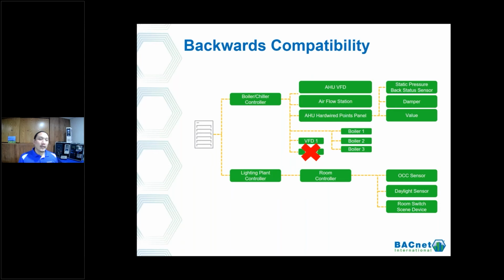Now you're looking, okay, I need to get a new VFD. But as you're looking, you find out that after 10 years they replaced that VFD with a new generation. You couldn't get that same exact one any longer. So you want to replace that VFD with a new one. When it comes to the backwards compatibility aspect of BACnet, you're able to go in, replace it with that new device, drop it in. It might take a little bit of work, but you'll be able to integrate and get it working in almost no time at all.